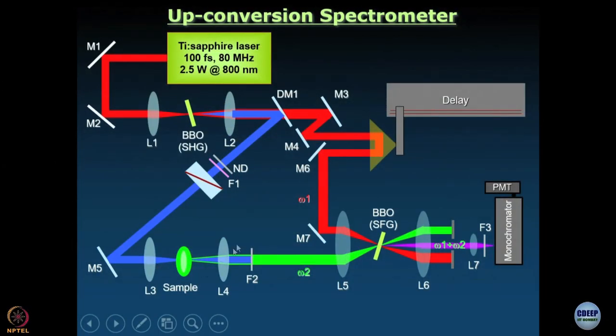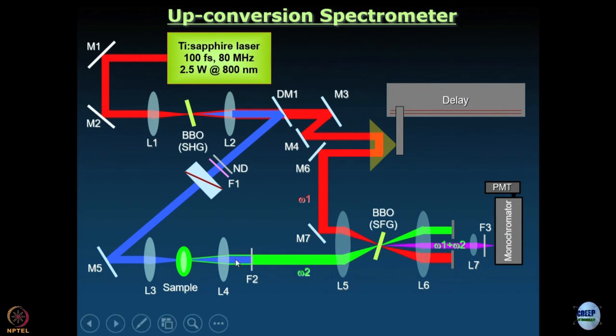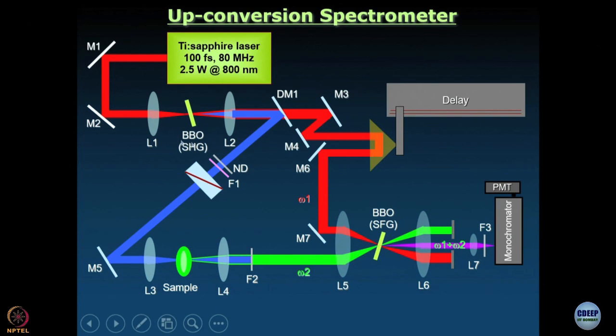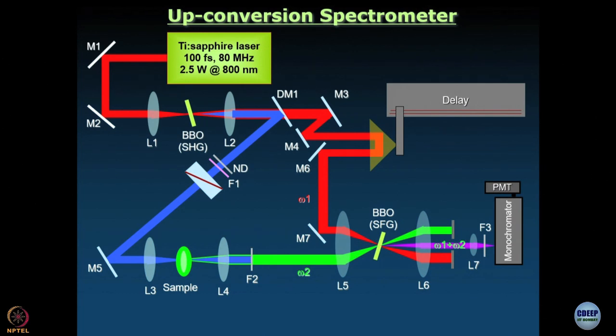Once again we have the familiar focusing-and-collecting optics arrangement. If alignment is perfect, a collimated beam emerges from the lens, but it is anything but monochromatic — it contains blue excitation light as well as fluorescence, and the blue light is more intense. That is why filter F2, a long-pass filter, is used: it cuts out the blue excitation laser light and allows only fluorescence to pass through. This lens then focuses the fluorescence onto the sum frequency generation crystal.